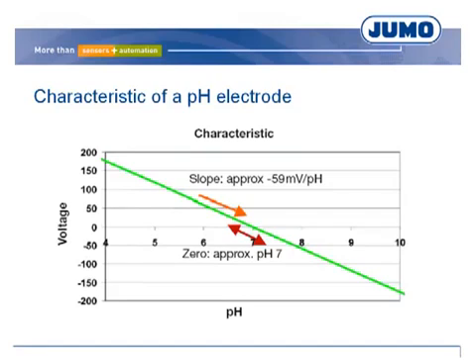The potential on the membrane glass results from the hydrogen ion concentration, or the pH value. The characteristic curve shows the potential depending on the pH value. The theoretical slope of the line is minus 59 mV per pH.